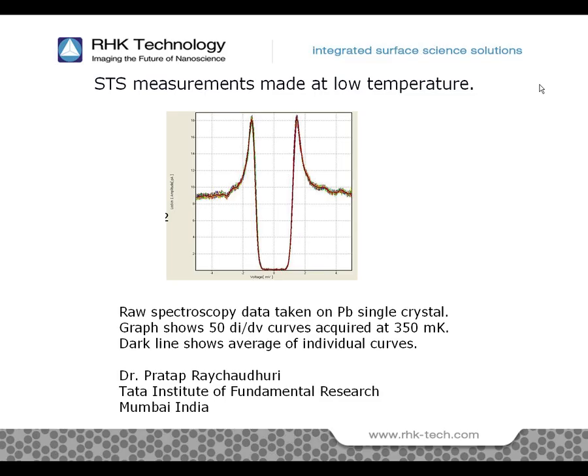With their old controllers, they needed to use an external lock-in and take many, many curves to average together due to variations from measurement to measurement. With the R9 system, they really had a big improvement because we have some very unique capabilities that we've put into the spectroscopic measurements to allow you to have much more repeatable gaps when you close the feedback loop between each different measurement. For instance, we turn the bias modulation off when you're stabilizing the gap. We turn the feedback loop very slow while you're setting the gap resistance before you freeze the feedback loop. So you can see on the curve, 50 curves were made with very, very little variation between them.